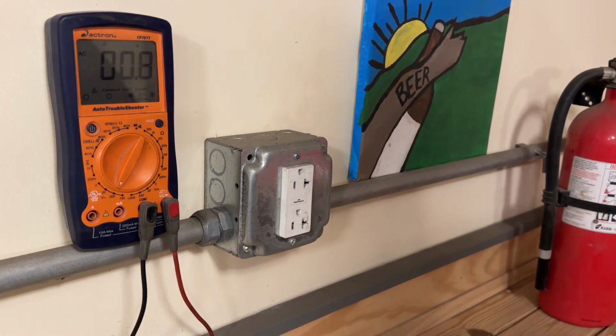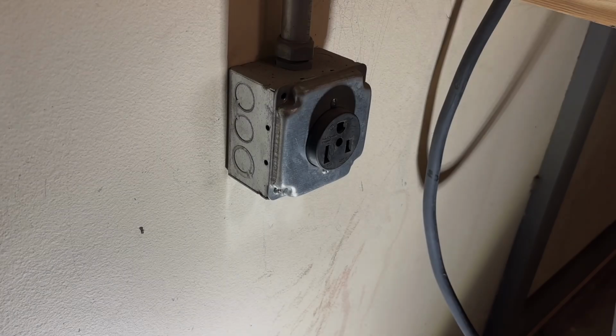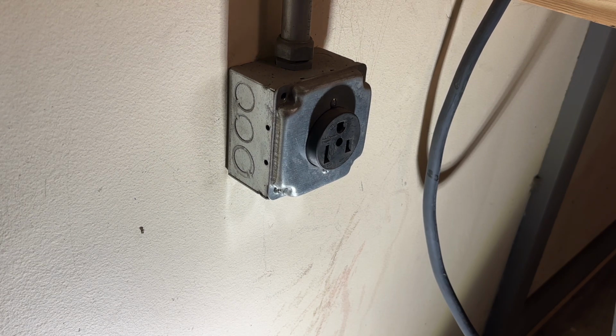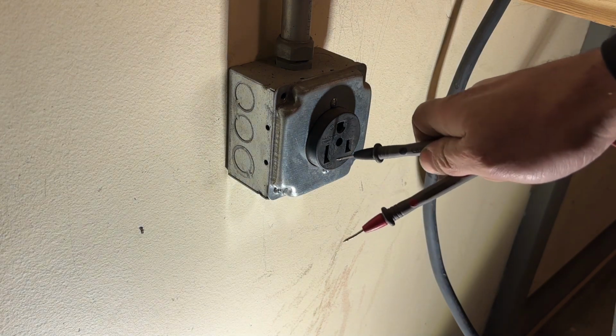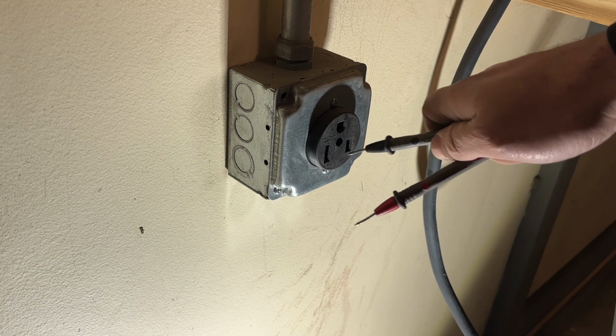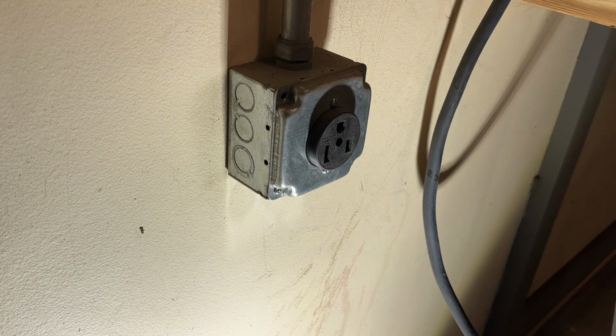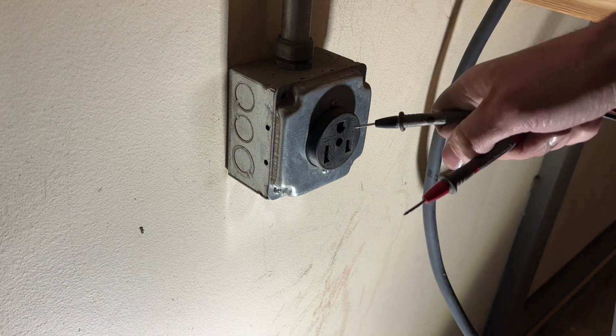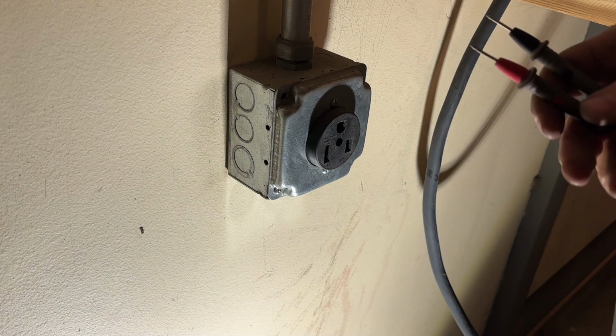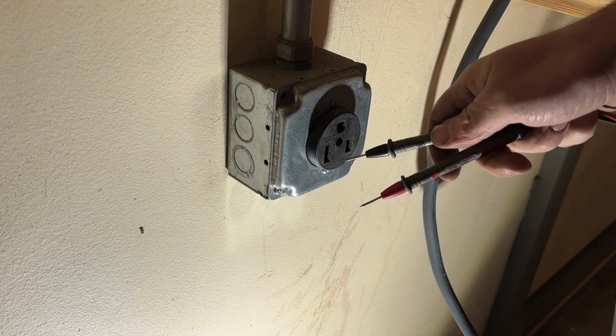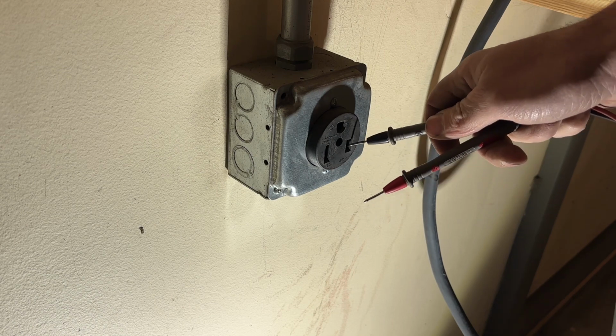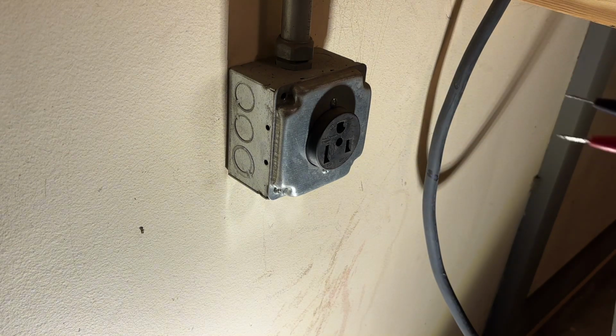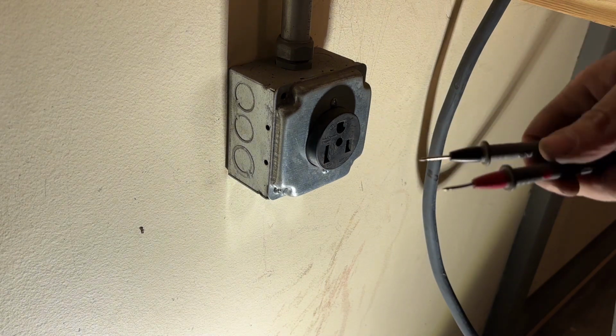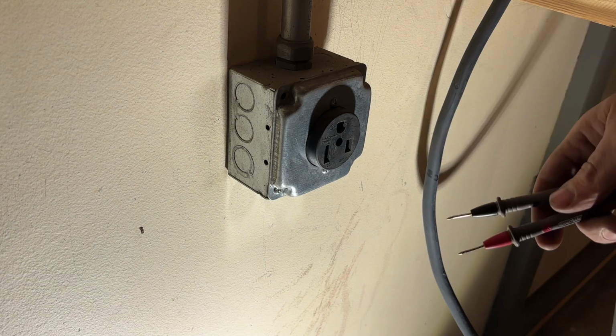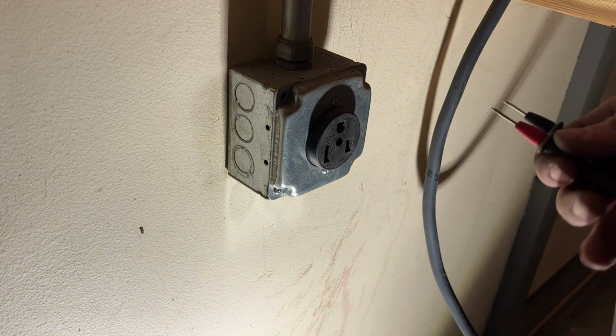Now let's look over at a 220 circuit. All right, here's one of my welding receptacles. This is a 220 or 240 volt circuit with two hots—even though one pin is smaller than the other, both are actually powered. That's how you get your 220 to 240 volts. The top pin here is the ground. If you're testing a dryer outlet, you'll actually have 4 pins: a ground, one hot, a second hot, and a neutral as well. Because this only needs to power 220 volt appliances, like my welder, you don't need a neutral wire—the wire itself is a neutral of sorts, I guess.